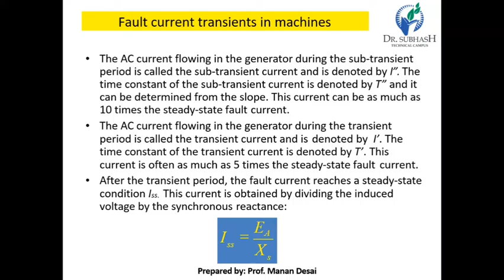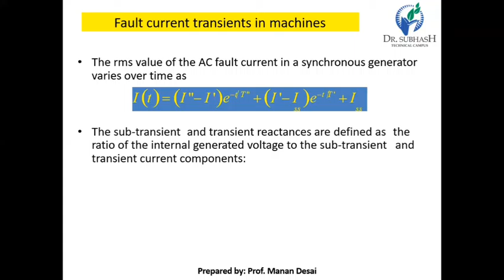It is possible to determine the time constant for the subtransient and transient periods. Now, fault current transients in machines: the AC current flowing in the generator during the subtransient period is called the subtransient current, and it is denoted by I double dash. The time constant of the subtransient current is denoted by T double dash, and it can be determined from the slope. This current can be as much as 10 times the steady state fault current.